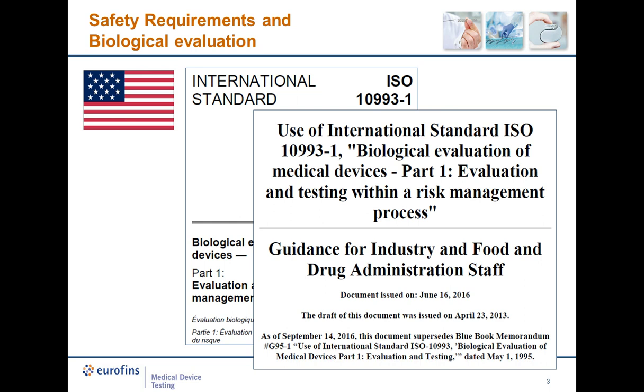In the US, the picture is a little bit more complicated, because FDA issued two years ago its own guidance, Use of the International Standard ISO 10993-1, adding peculiar requirements for the US market. In any case, ISO 10993-1 describes the general principles governing the biological evaluation within a risk management process, the general categorization of devices based on the nature and the duration of their contact with the body, the evaluation of existing relevant data, the identification of gaps in the available data set on the basis of a risk analysis, the identification of additional data sets necessary to analyze the biological safety, and finally, the assessment of the safety of the medical device.